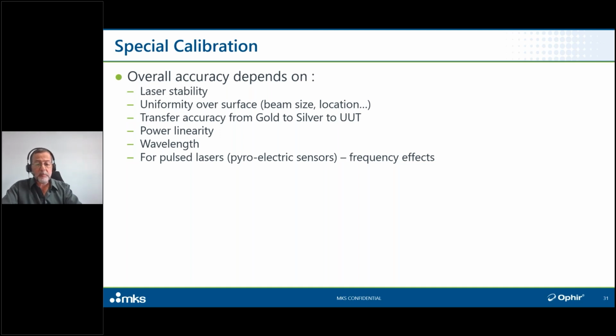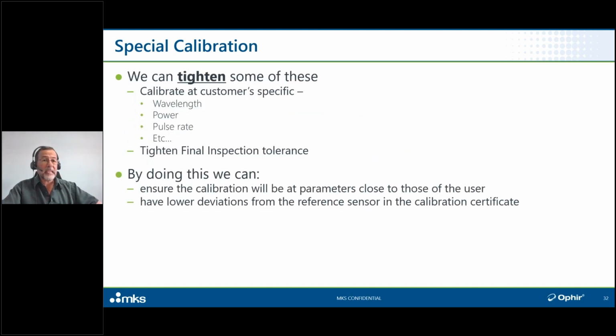So most of these are eliminated from the calibration process, but the user's application might not sit at exactly these conditions of wavelength, power, pulse frequency, or whatever. So if we can instead tighten some of these and calibrate at the customer's exact wavelength, which might not be the standard wavelength or one of the standard wavelengths at which this sensor model normally gets calibrated, wavelength, power, pulse rate, any of the parameters.